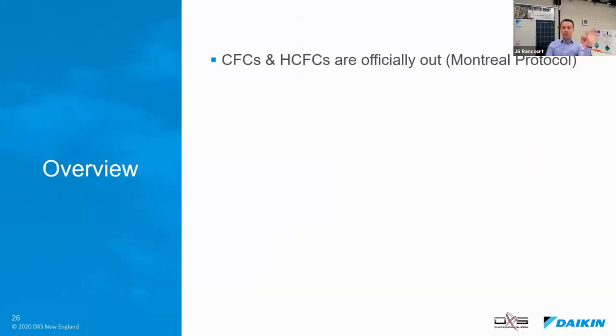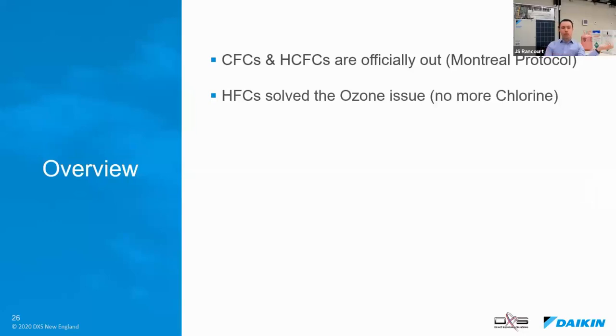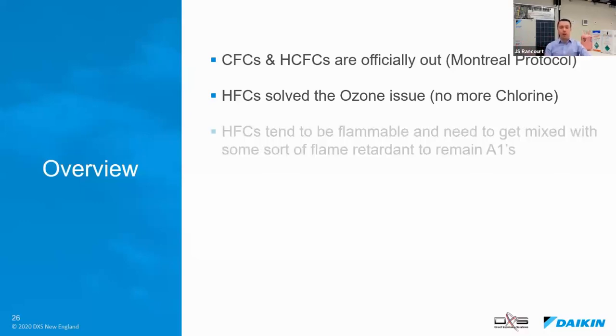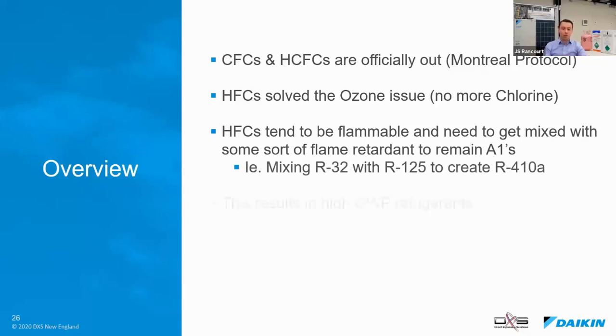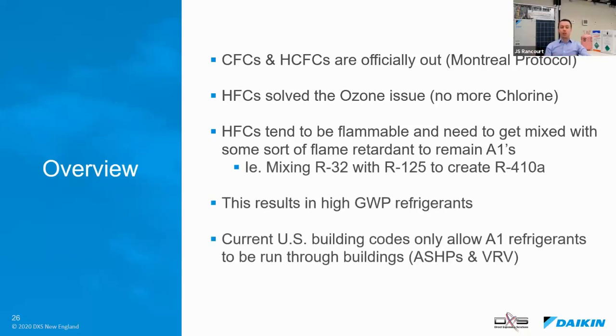All right, let's take a breather. A bit of overview of what we've seen so far. CFCs, HCFCs, those are out. HFCs solved our ozone issue. The Montreal Protocol and its follow-ups mean our ozone is already rebuilding at a faster pace than expected, and by the end of the century, we should be fully repaired. However, HFCs tend to be flammable, and they need to be mixed with some sort of flame retardant to remain an A1 refrigerant, i.e. R410A. This results in higher global warming potential refrigerants. And the issue is our current building codes only allow A1s in the building, which air source heat pumps and VRV do.